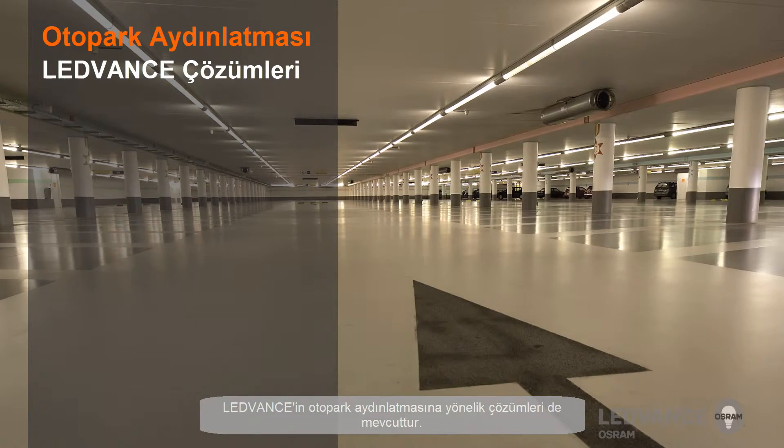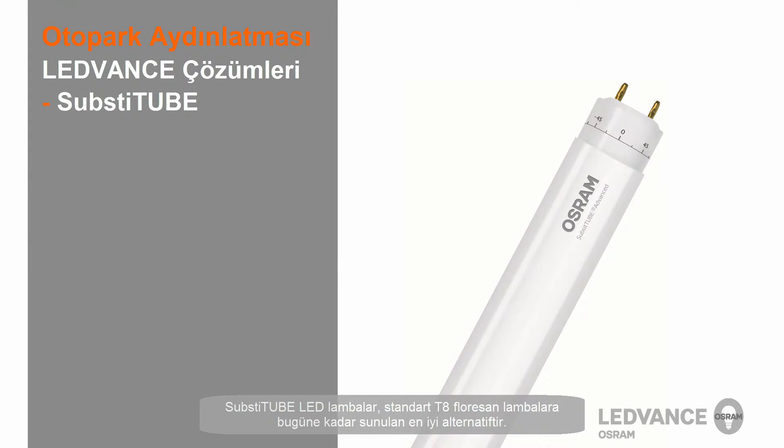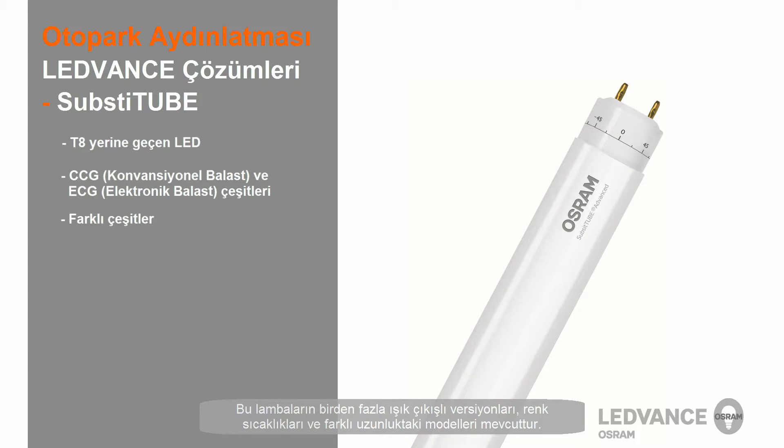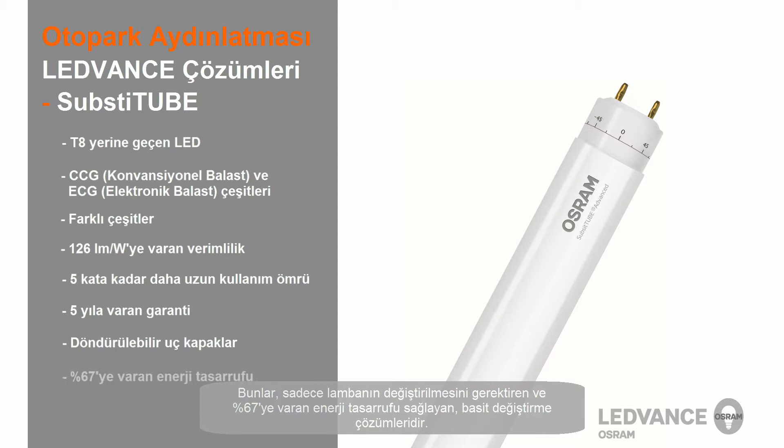LEDVANCE has solutions for illuminating parking garages. The Substitube LED lamps are now more than ever the ideal alternative to standard T8 fluorescent lamps. These are LED T8 lamp solutions that are compatible and can be installed on existing control gear or directly connected to mains voltage. They are available in multiple light output versions, color temperatures, and multiple lengths. They now shine with increased efficiency, up to 5 times longer lifetime than classic fluorescent lamps, better guarantee conditions, and on request with rotatable end caps for precise setting of the desired beam angle. These are simple replacement solutions with up to 67% energy savings that only require a simple lamp change.